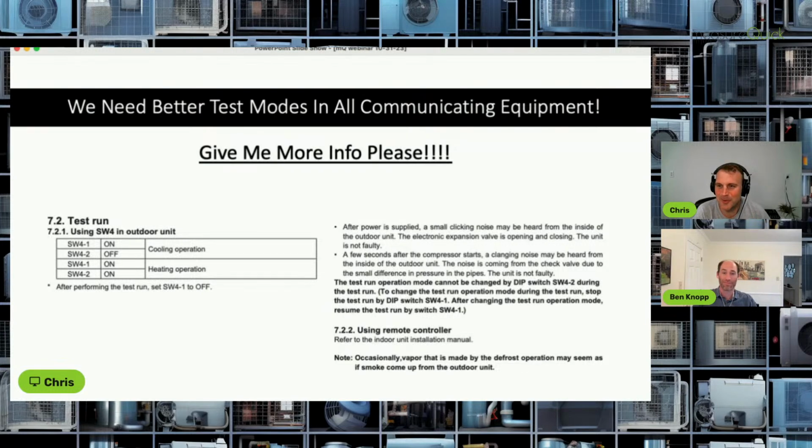And there's more literature in this manual about megging out the compressor than there is about operating it in test mode, so you can check it out with independent third-party tools to make sure that the refrigerant charge is good while it's running at 100%. It's bad. I'm seeing this a lot, and it's annoying.